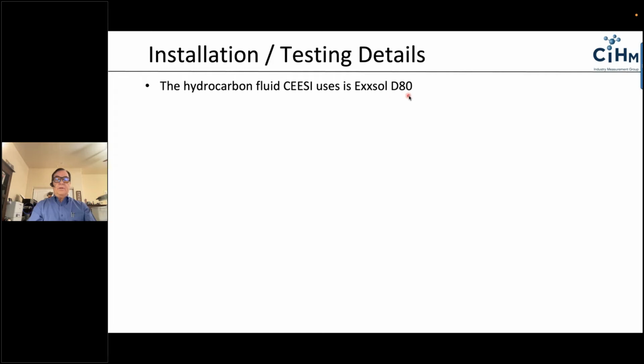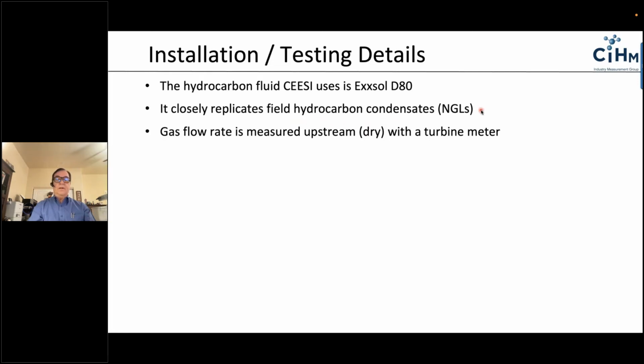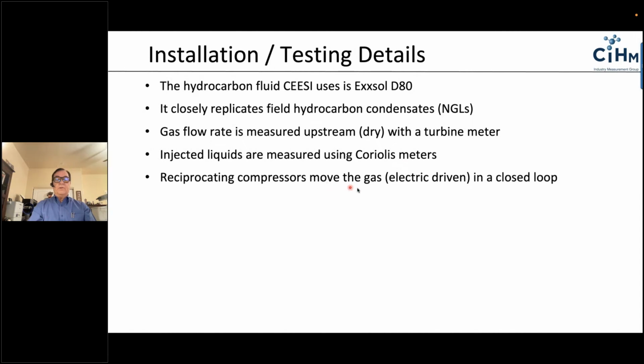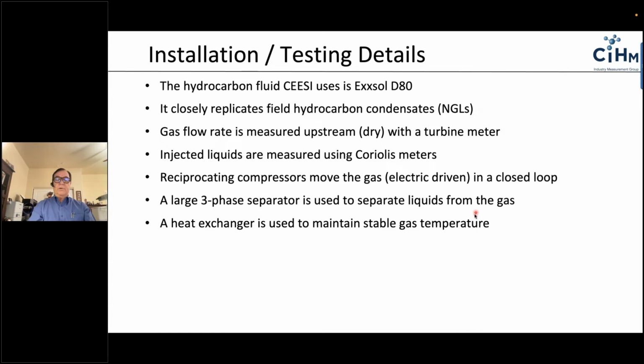The hydrocarbon fluid, as I mentioned, is a fluid called Exxsol D80. The reason it's used is because it closely replicates NGLs without the volatility of an NGL. The gas flow rate measurement at the facility is done with a turbine meter upstream of the meter under test, so it's under dry conditions with no liquids. Liquids are injected into the loop after the turbine meter using a Coriolis meter for mass measurement. Reciprocating compressors move the gas in a closed loop circuit. It's an electrically driven compressor system. They do have a 3-phase separator to separate the water, the hydrocarbon fluid, and the natural gas. So this system can run basically pretty much all day.